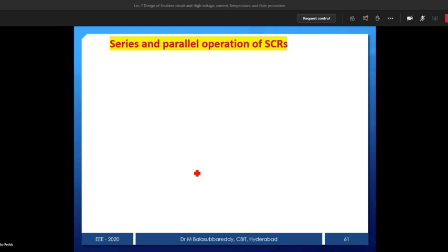Suppose I want to connect some 1000 volts of DC. Each panel has some voltage rating, maybe 230 volts or 40 volts or 24 volts based on your panel. Those panels are connected in series to get your required voltage level. Once you get the required voltage level, we call it a string. So 10 or 20 panels, based on your level of power installation capacity, are connected as one string.